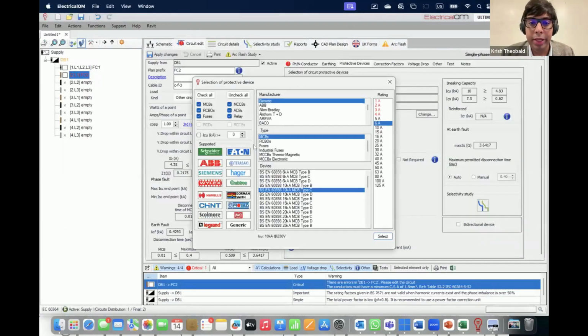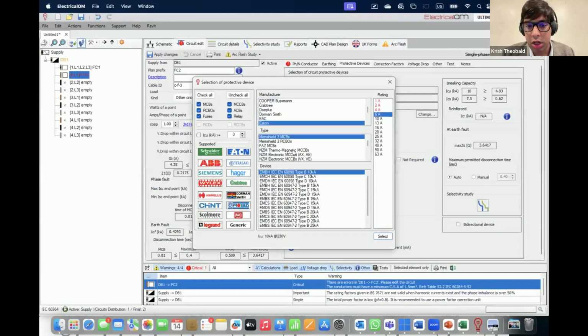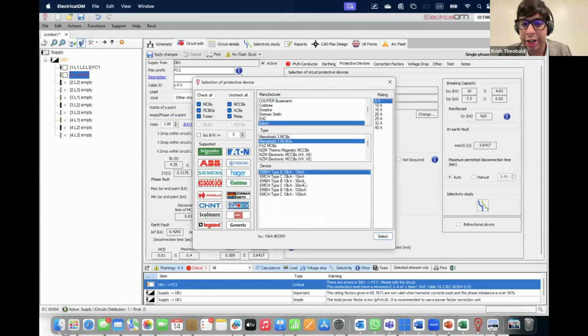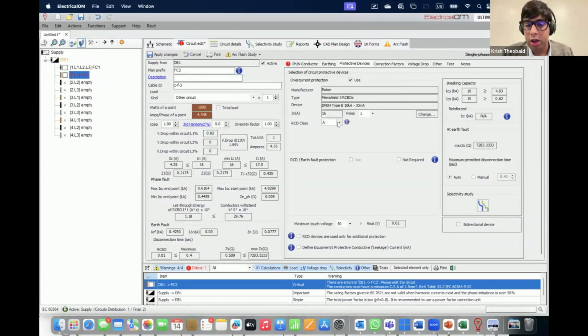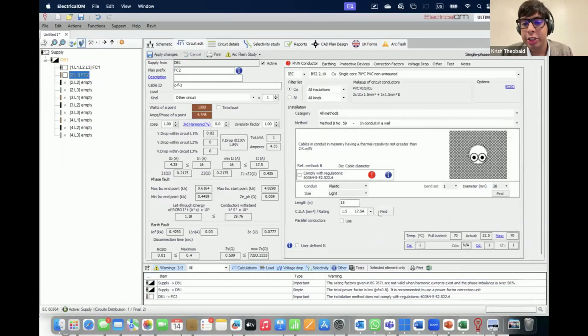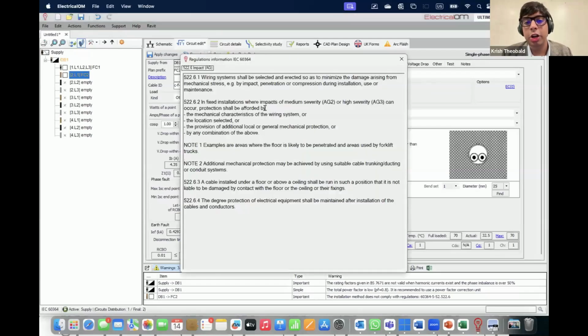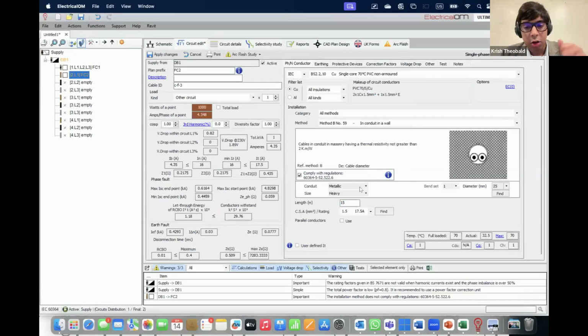We'll choose a D16 RCBO this time because you'll need additional protection. You can select type AC, AF, and you see by default it selects type AC. Say we run it in steel conduit, so metallic conduit, heavy, 25 millimeters, and we can put in a number of bends and it will do that calculation as well. Now it's asking us, is the circuit protected against mechanical damage? It's a requirement of the standard. So if I say yes, we're good to go there.